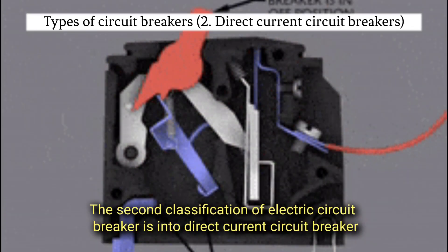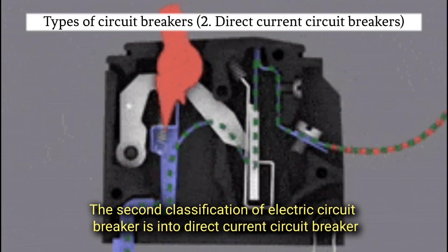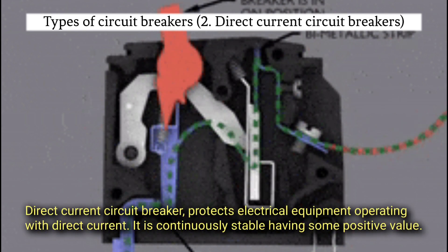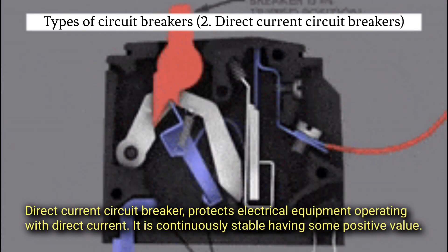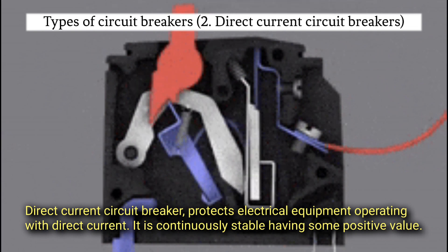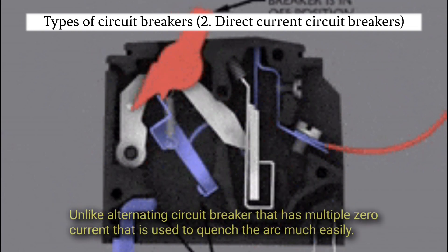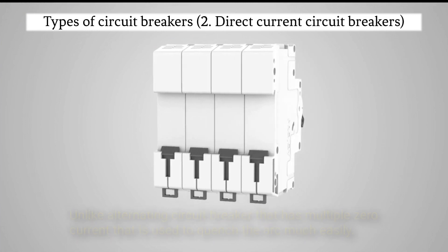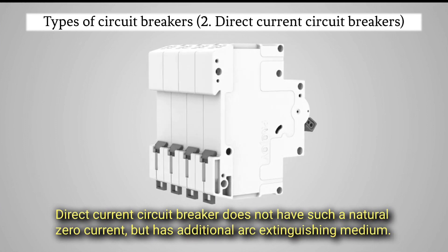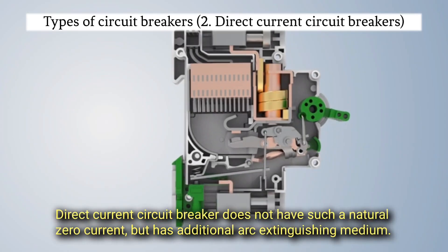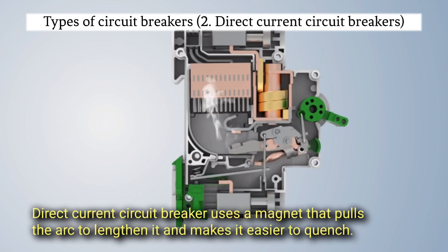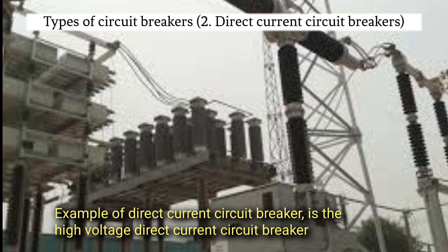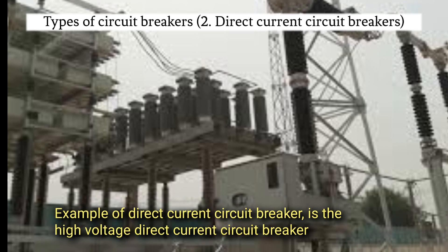The second classification of electrical circuit breaker is the direct current circuit breaker. Direct current circuit breaker protects electrical equipment operating with direct current. It is continuously stable having some positive value. Unlike AC circuit breakers that have multiple zero currents used to quench the arc much easily, direct current circuit breakers don't have such natural zero current, but have additional arc extinguishing mediums. DC circuit breakers use a magnet that pulls the arc to lengthen it and makes it easier to quench. An example of a direct current circuit breaker is the high voltage direct current circuit breaker.